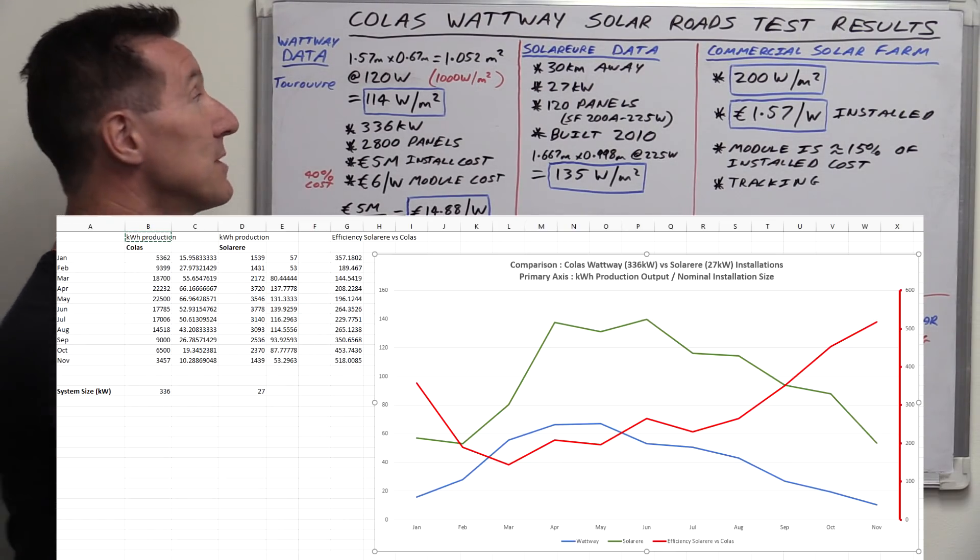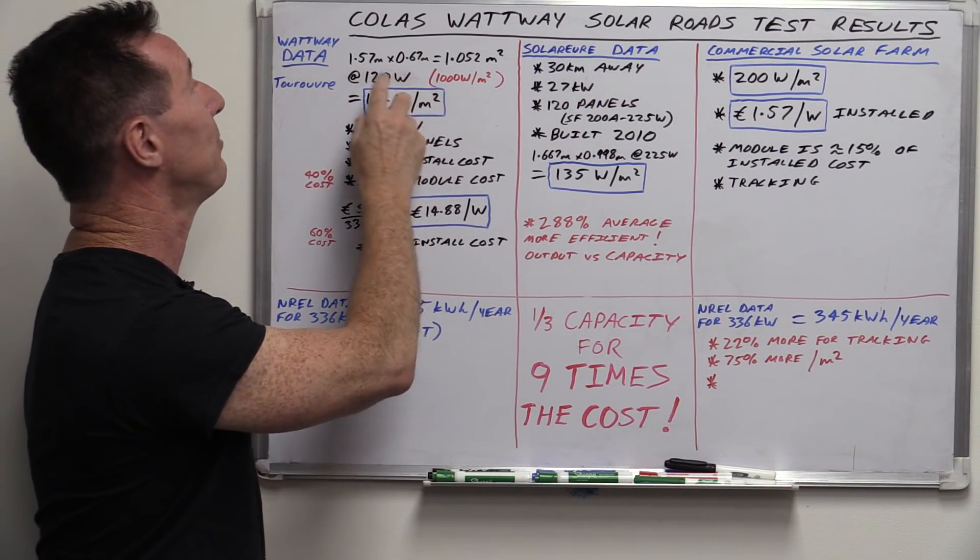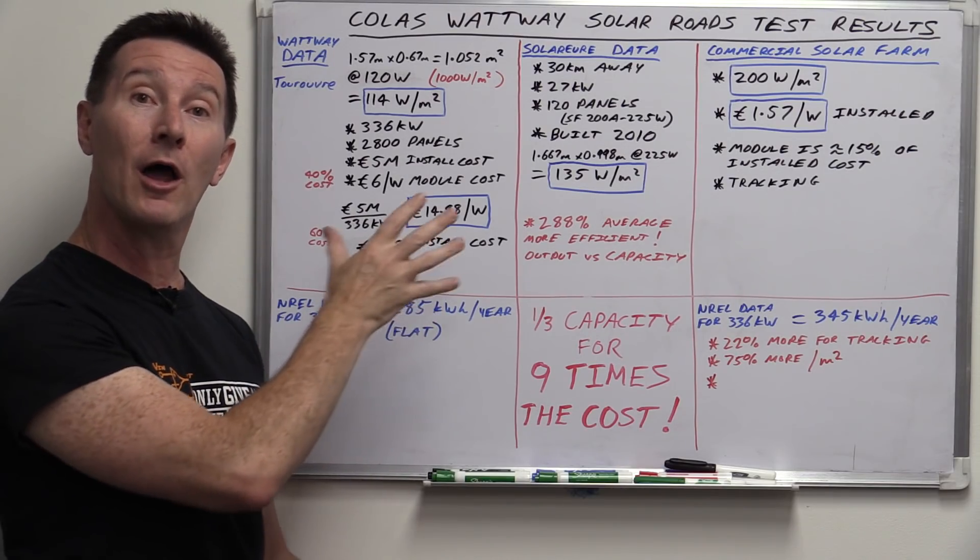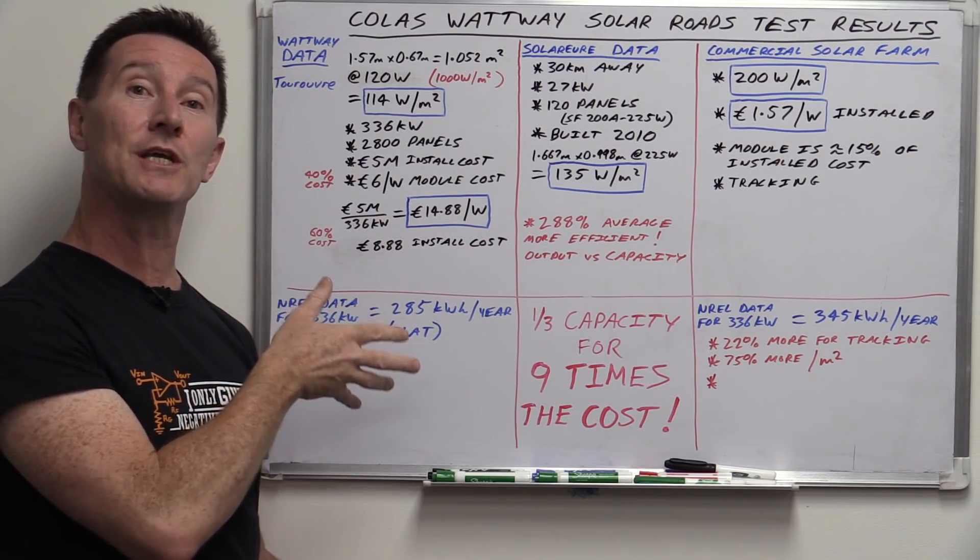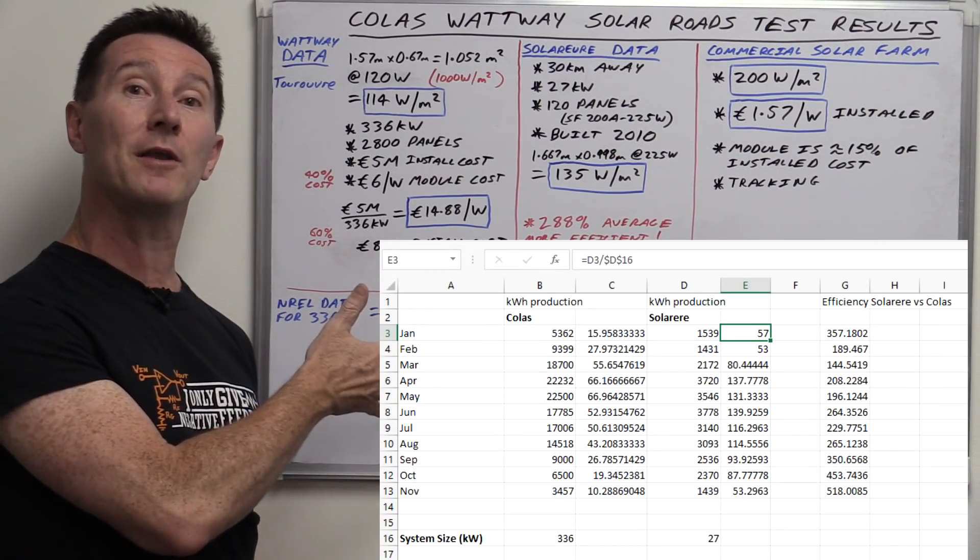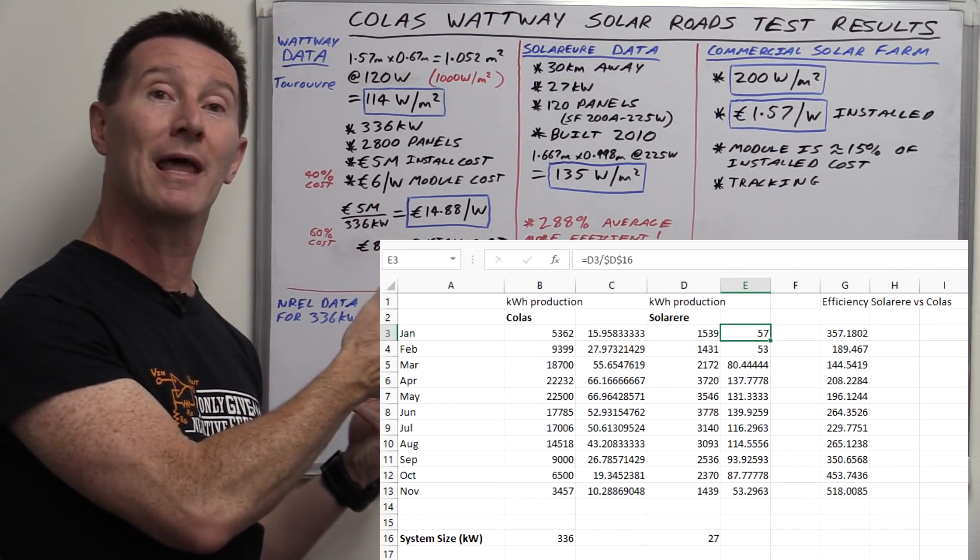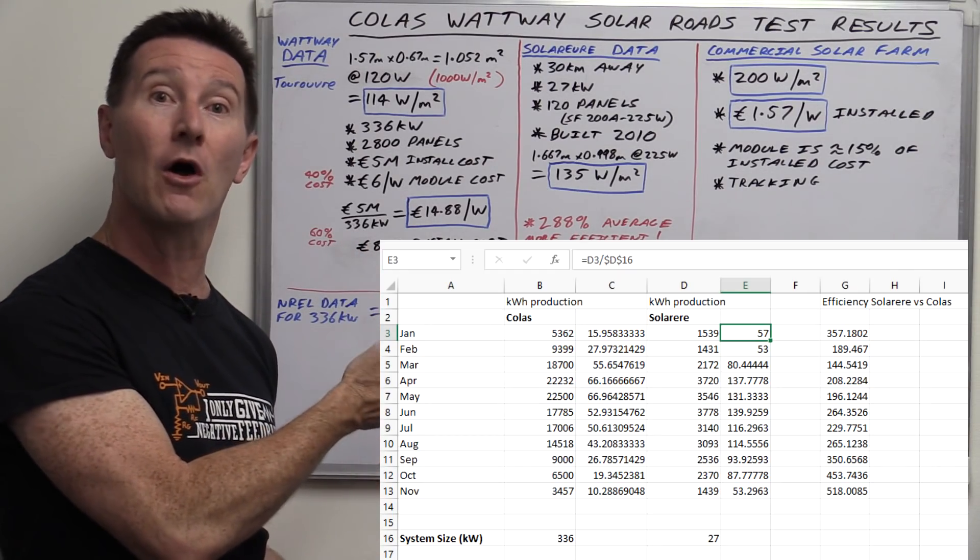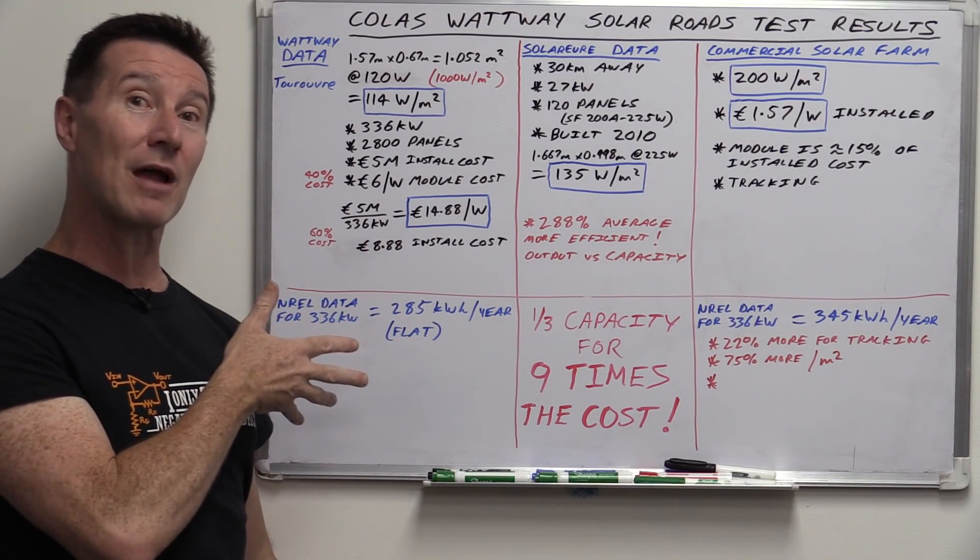So what I've done is actually got a spreadsheet of the test results from January through to November, or the production output results for these two systems. Even though they are greatly by an order of magnitude different in size here, it doesn't matter. I'm accounting for that in the spreadsheet. So it's basically the production output divided by the nominal system size. So that's a nominal output per unit size, so to speak.